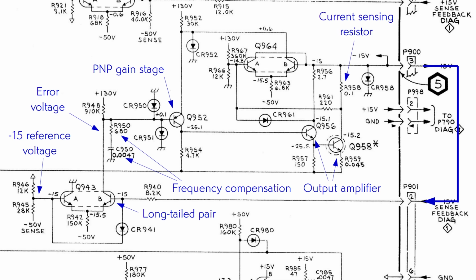There's a 0.1 ohm resistor whose voltage drop measures the current—a 0.1 volt drop would be 1 ampere. A long-tailed pair is driven from the two sides of this resistor. If the current is too high, the pair begins to sink current from resistor R952, which reduces the negative voltage out of the PNP gain stage, cutting back the output voltage so the target current is never exceeded.